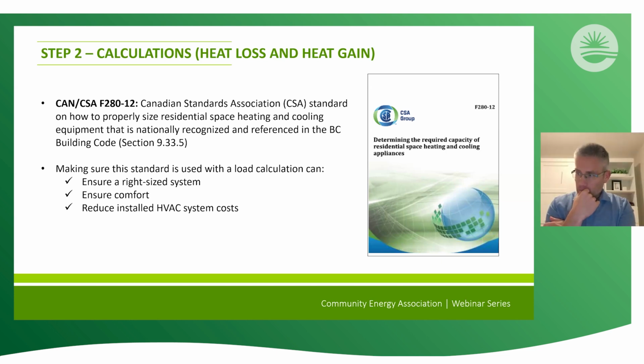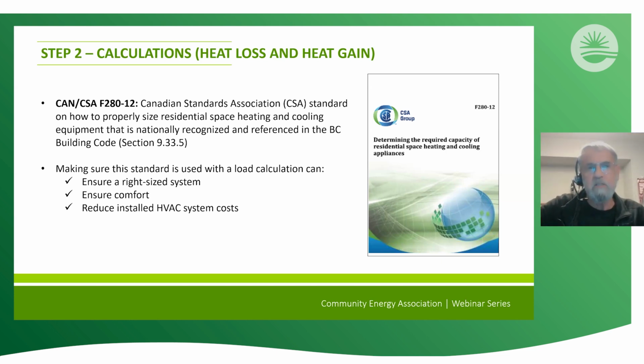It may not need to be higher, but a gas furnace without a coil that is attached to a heat pump will have a lot less resistance. And so it can deliver more heat because it's only going through a heat exchanger. Since you put a coil in that ductwork, you're adding a lot more resistance. So that's one thing. The other thing is, in order for the refrigerant to do its job, it has to change states. It has to go from a gas to a liquid and back and forth, depending on the season. In order to do that, it needs a certain amount of airflow. Nominally, it's about 400 CFM per ton. Every 12,000 BTUs is a ton, and there's about 400 CFM, give or take, depending on the equipment, a little less or a little more.